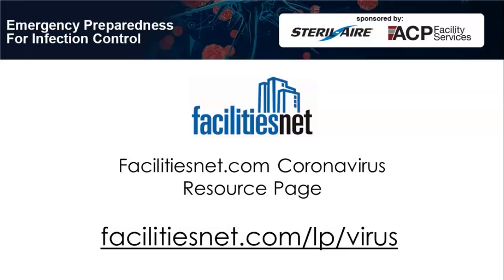Certain people and certain companies don't necessarily engineer to the same dose as everybody else. I wish it was more standardized, but it is not, and neither is it really through ASHRAE. So with that, it depends on how many times you cycle your air through. You can never be too safe. We have healthcare facilities where not only do we treat air handling units, but we treat the ducts themselves, and even the upper air spaces. All three of those strategies are recommended by ASHRAE. They all have their benefits, and they all have their drawbacks and kind of what you can achieve with them.